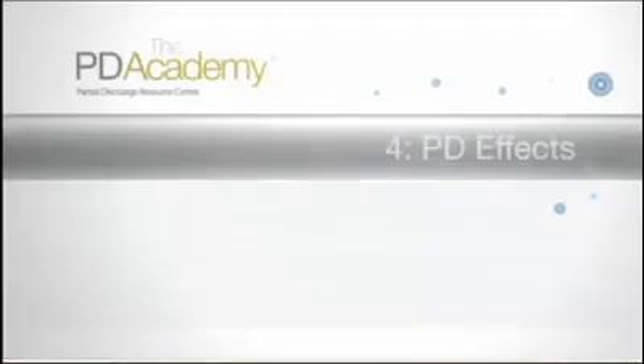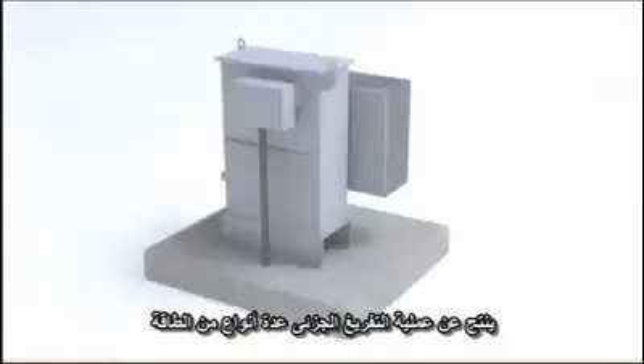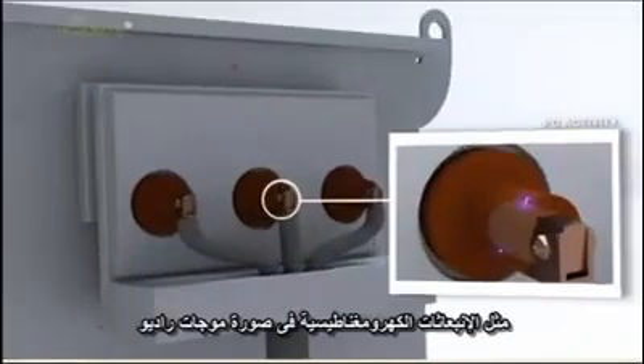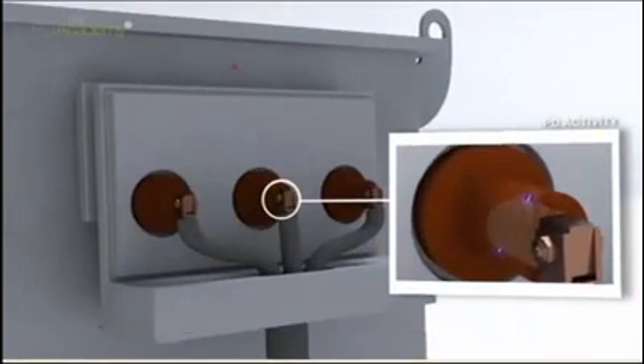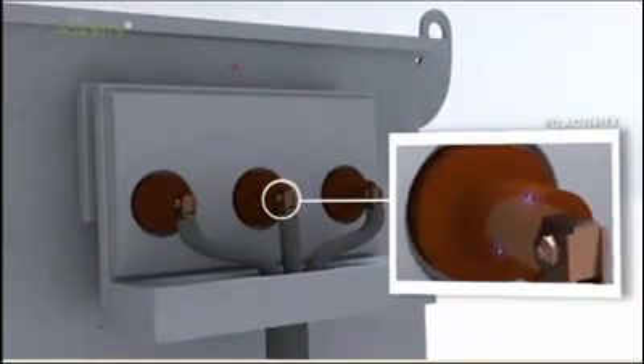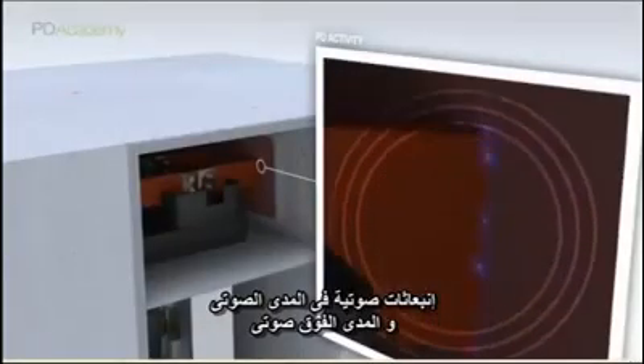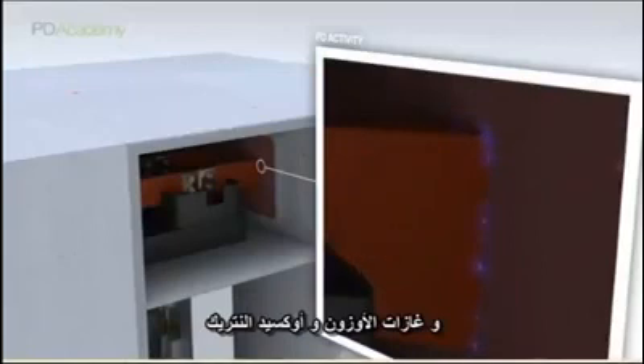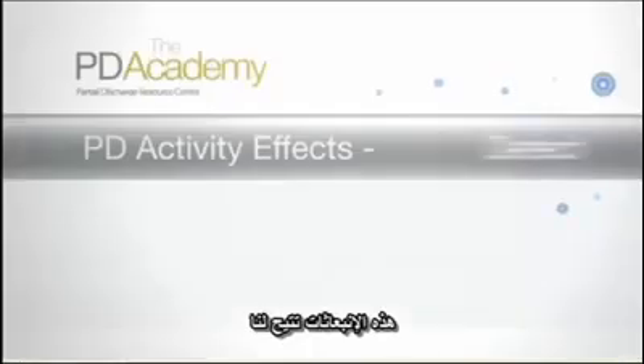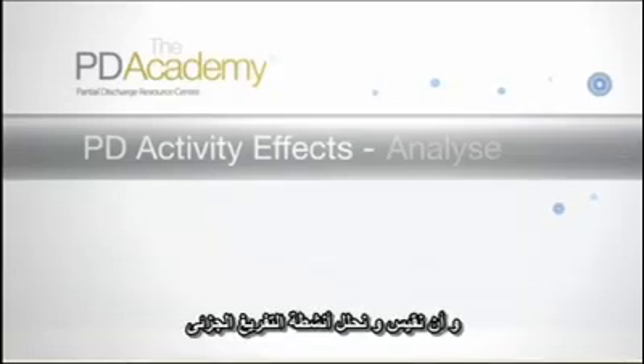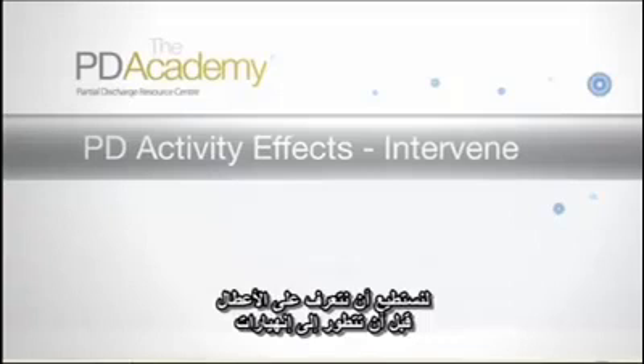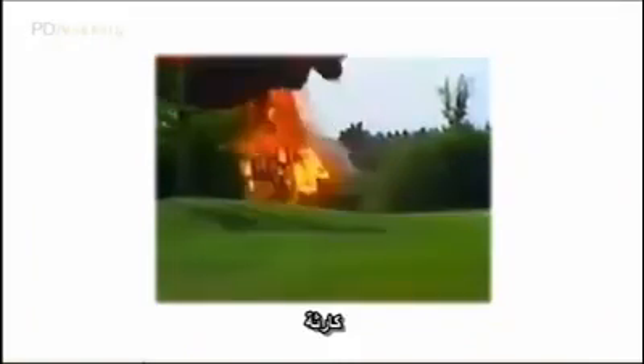PD effects. Partial discharges emit energy in several ways, producing electromagnetic emissions in the form of radio waves, light and heat, acoustic emissions in the audible and ultrasonic ranges, and ozone and nitrous oxide gases. And these emissions enable us to detect, locate, measure, and analyze PD activity, so we can identify faults before they develop into failures. Because once present, the damage caused by PD always increases, leading to asset failures, outages, and if protection systems fail, disaster.